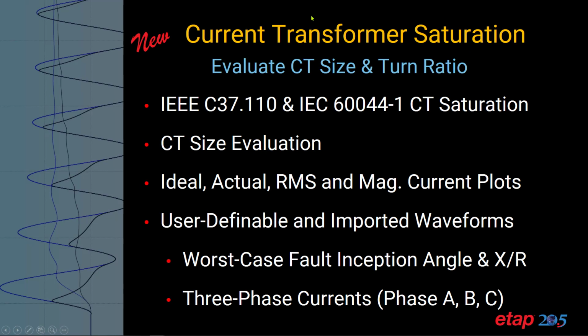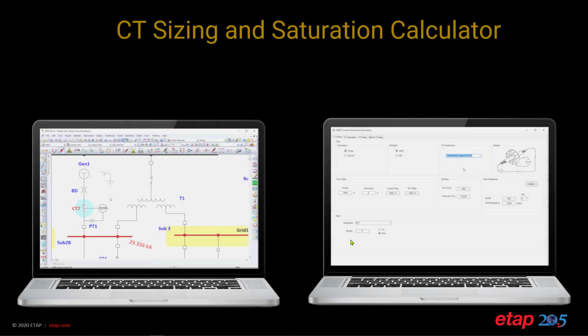Another new capability that has been added to ETAP 20.5 is current transformer saturation, which is used to evaluate the current transformer size as well as the turns ratio. And this is done based on IEEE C37.110 as well as IEC 60044-1 in order to determine the CT saturation, and based on the probability of CT saturation, we can evaluate the CT size. From this tool, you can also get the ideal, actual, RMS, and the magnitude for your current plots. You can also use it to import waveforms in order to see the worst case fault inception angle and plot three-phase currents, that is phase A, B, and C.